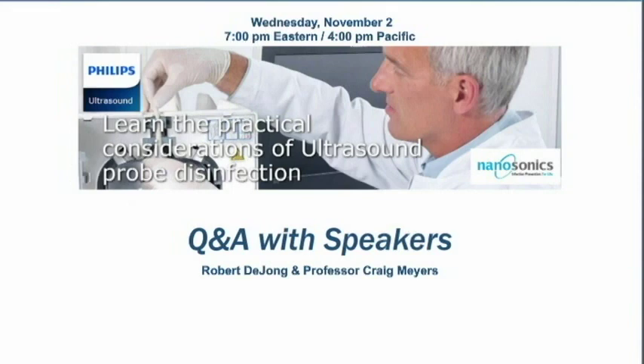Thank you very much. The question reads, the last time I checked, most of the surface probes were not approved for high-level disinfection. Are there methods available now to HLD the surface probes? Well, yes, if you take a look at the manufacturers, they'll tell you the different things you can use on the transducers, and some of those will be high-level disinfection. Again, to me, when you really start to read about things like VRE and MRSA and C. diff and how it gets spread, but more importantly, how long they live on surfaces, and we're talking weeks to months, it sort of makes you want to make sure you're really cleaning those transducers. So, again, at our institution, we try to do high-level disinfection on every transducer when possible.